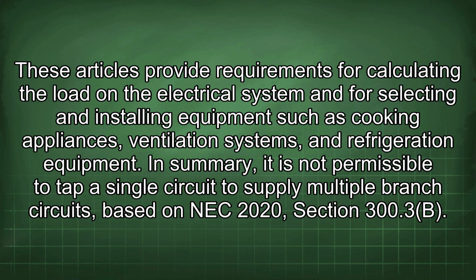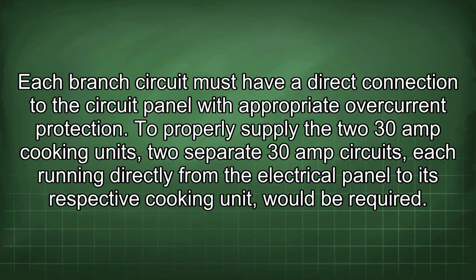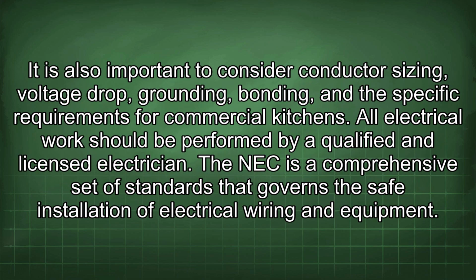Section 300.3(B). Each branch circuit must have a direct connection to the circuit panel with appropriate overcurrent protection. To properly supply the 2 30-amp cooking units, two separate 30-amp circuits, each running directly from the electrical panel to its respective cooking unit, would be required. It is also important to consider conductor sizing, voltage drop, grounding, bonding, and the specific requirements for commercial kitchens. All electrical work should be performed by a qualified and licensed electrician.